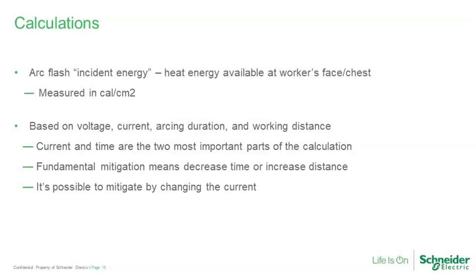Again, we've already mentioned that the energy is calculated based on the power times the time. The longer that fault lasts, the more energy is going to be delivered to the equipment or to the worker who's standing around. So fundamentally, when we're talking about arc flash mitigation, in many cases we're looking at ways to either decrease the amount of time that the fault stays on the system or increase the distance between the worker and that fault source. It's kind of the original social distancing, right? If we can move the worker away from the source of the arc, you decrease the amount of energy they're exposed to and reduce the risk as a result.